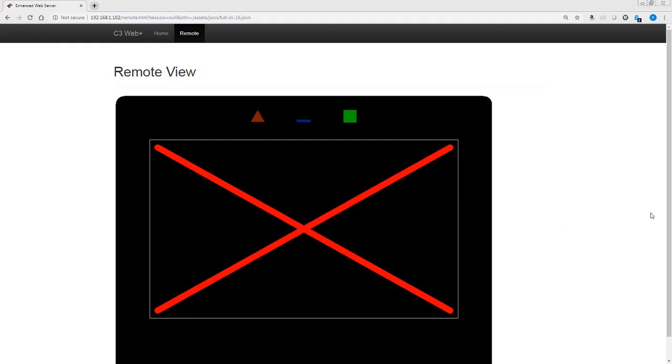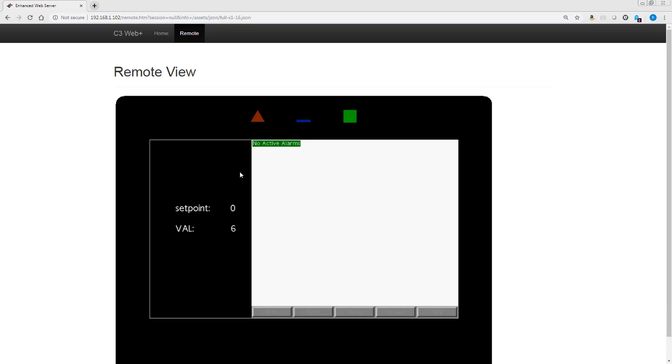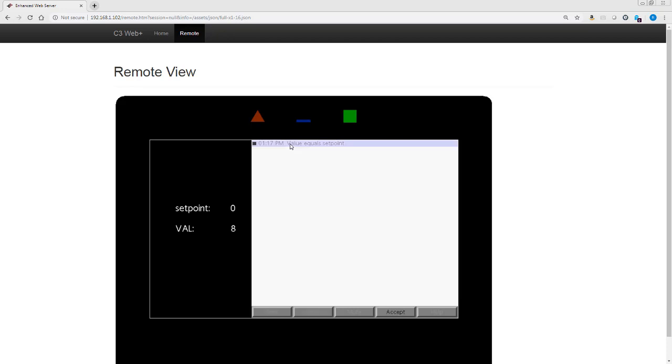We will see that right now the value doesn't equal zero, so no active alarms. But as soon as it hit zero, it popped up, turned red, which means it's active. And now it no longer matches zero, so that went to gray. If I want to accept this alarm, I click here and choose accept. And we're back to no active alarms until the value reaches the setpoint again. That's how that works.